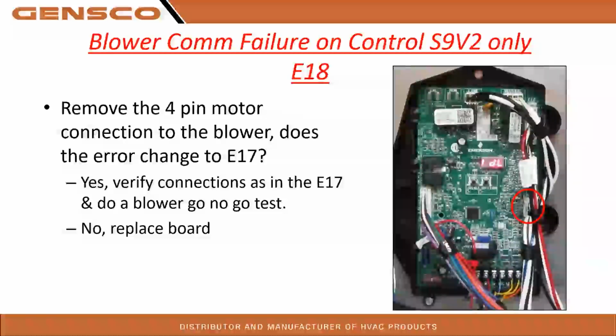All right, so blower comm failure, control S9V2, so this is an E18. We're going to remove the 4-pin motor connection to the blower. Does the error change to an E17? If yes, verify the connections as in the E17 failure. We're going to do a blower go/no-go test with a TechMate tool, a Zebra, whatever you've got, or you can even hardwire if you have to, a little bit harder of a process. If the blower motor comes on during that go/no-go test, then you're going to replace the control board.